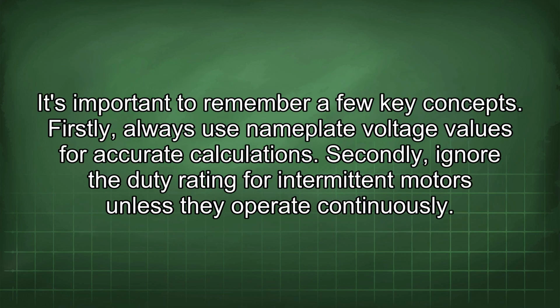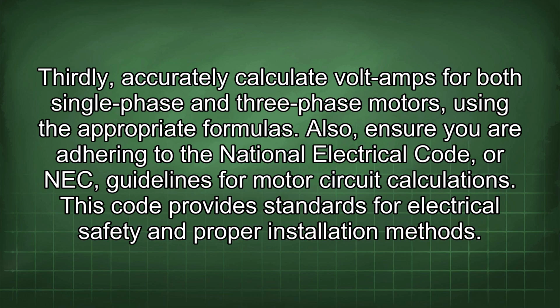It's important to remember a few key concepts. Firstly, always use nameplate voltage values for accurate calculations. Secondly, ignore the duty rating for intermittent motors unless they operate continuously. Thirdly, accurately calculate volt amps for both single-phase and three-phase motors using the appropriate formulas. Also, ensure you are adhering to the National Electrical Code, or NEC, guidelines for motor circuit calculations.